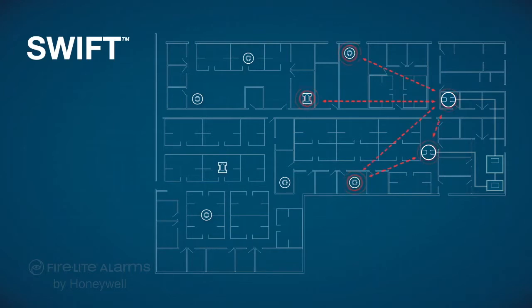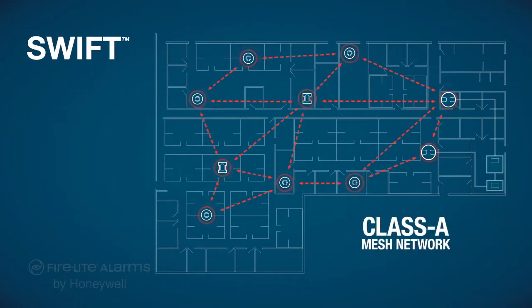Communication is established between the gateway and nearby devices. Communication is also established from device to device. The Class A mesh network within the SWIFT system creates a child-parent relationship so that each device has at least two parents providing a second redundant path for communication.